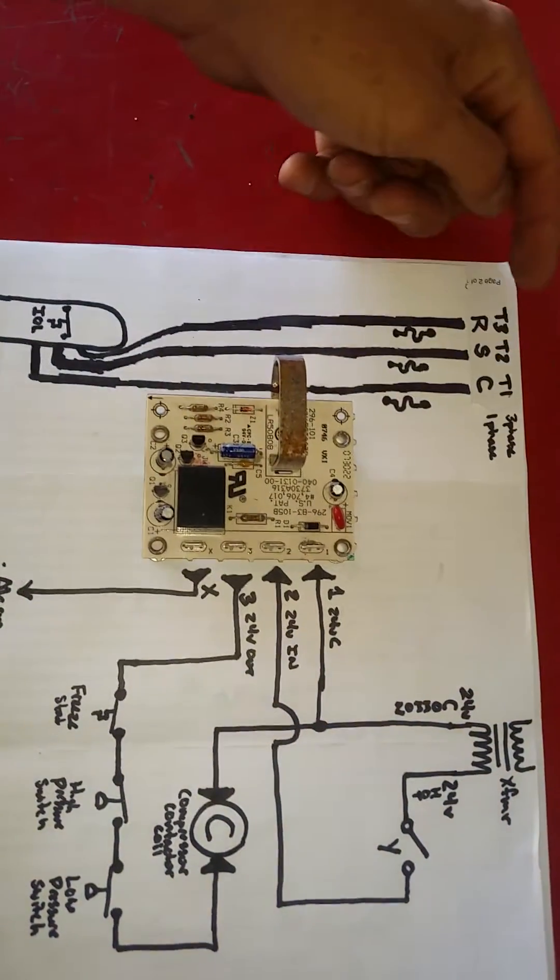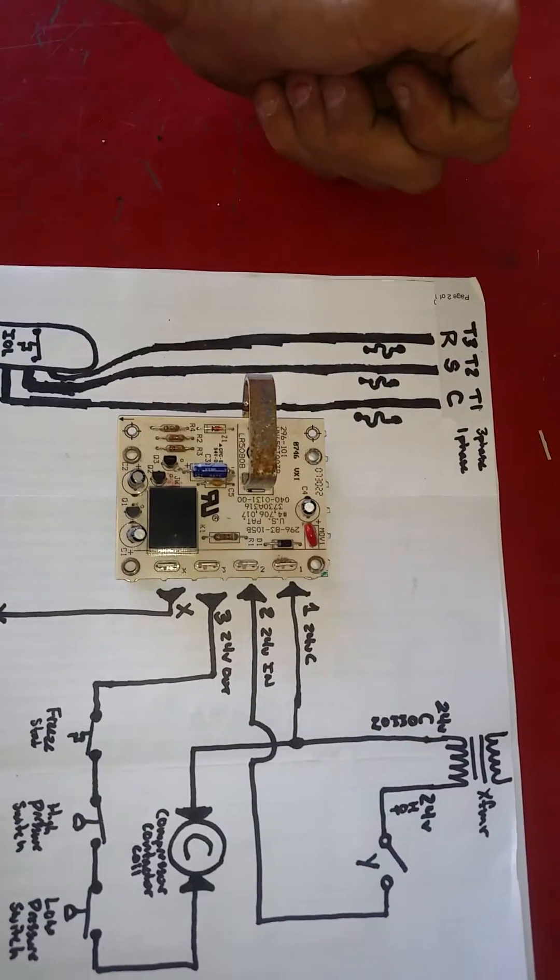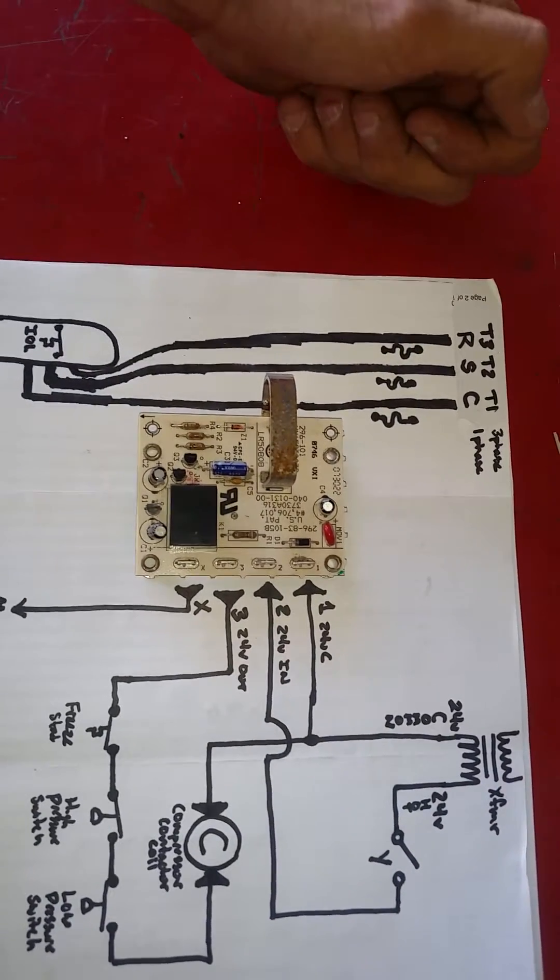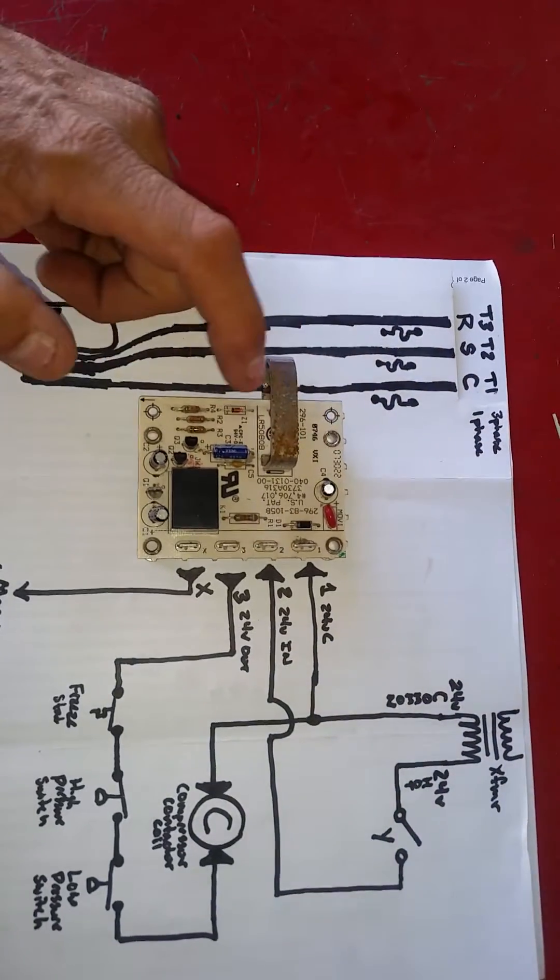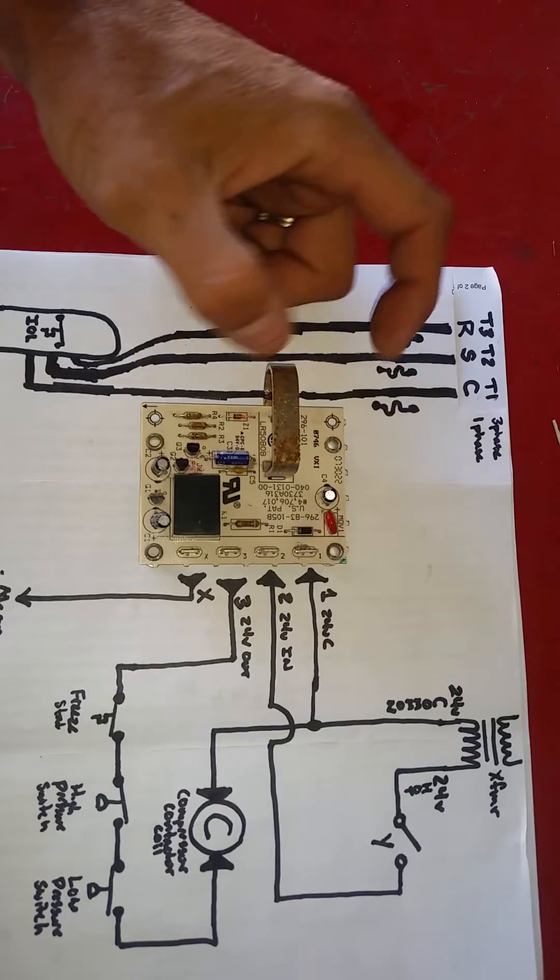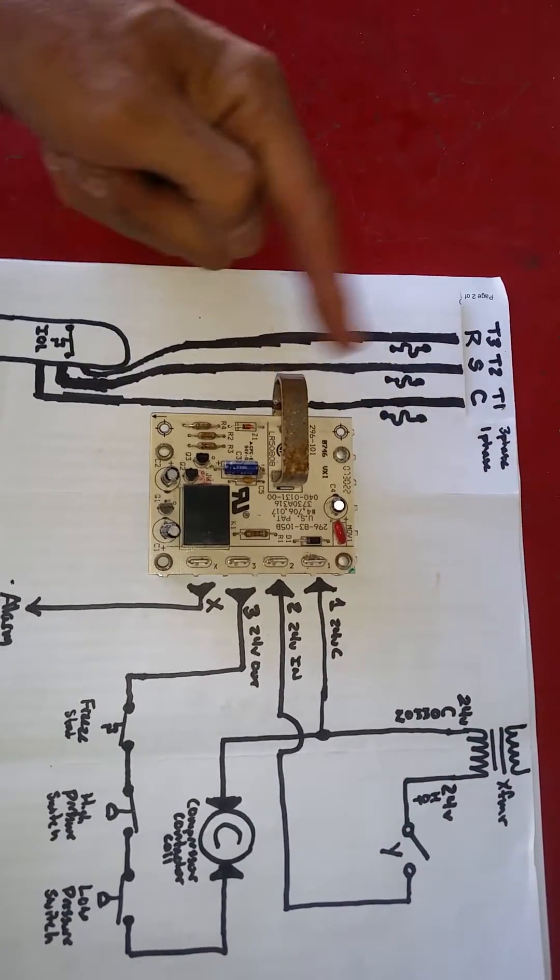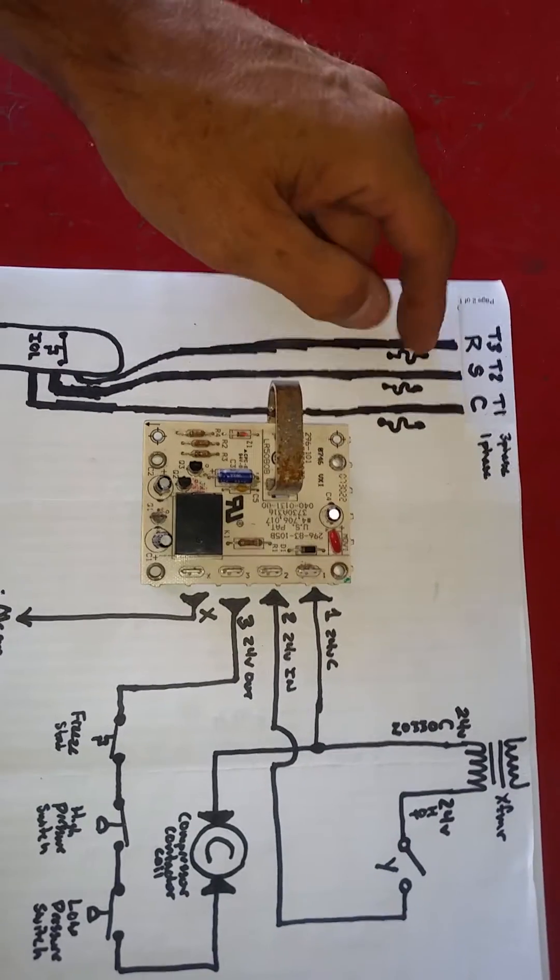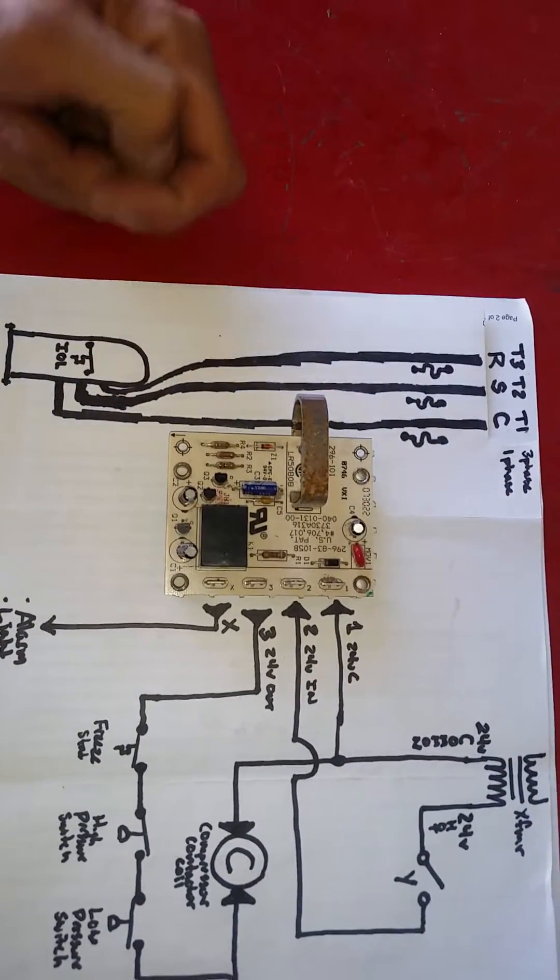Now if you notice, we have, either if it's a three phase, T1, T2, T3, or it's a single phase compressor, we'd have our common start and run. And usually our current sensor is wrapped around, or it will be around, our black or our common wire on our single phase, or any one of the three, if it's a three phase, leads going to the compressor.